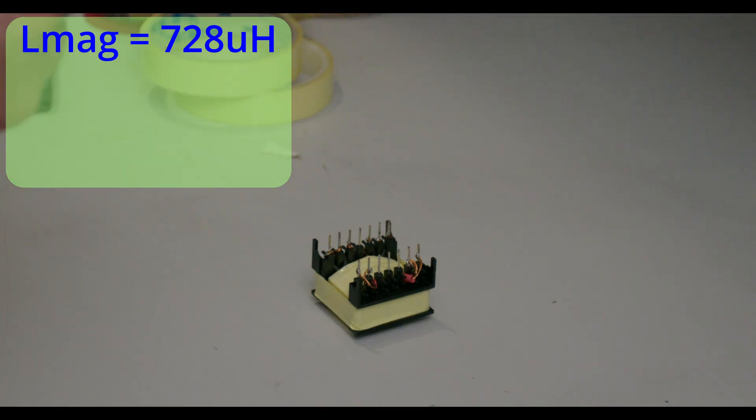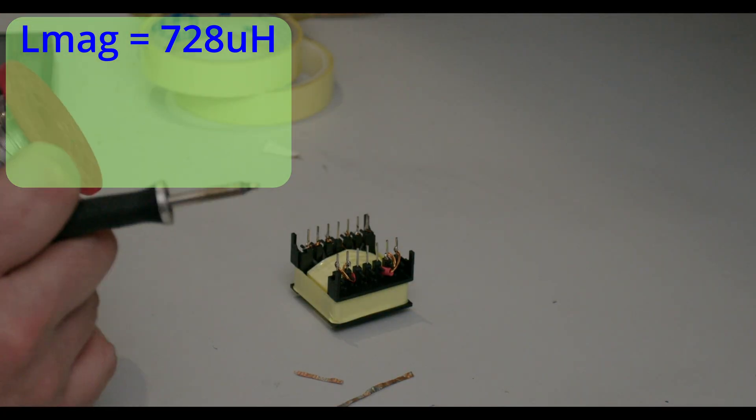We have already measured the primary magnetising inductance at 728 microhenries, which is in spec. This is just the inductance of the primary winding with all other windings open circuit.